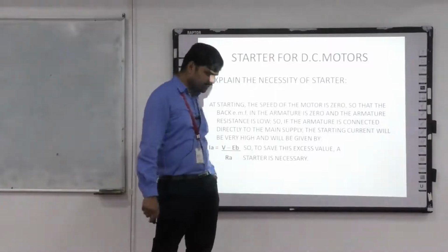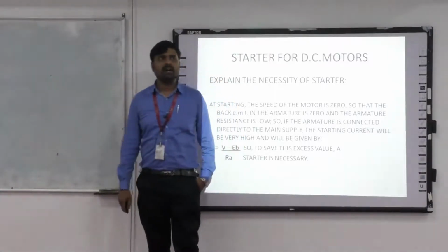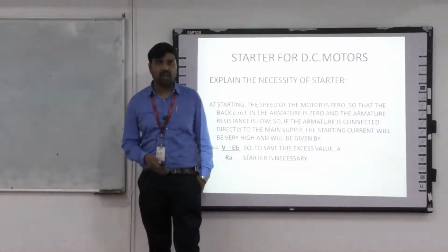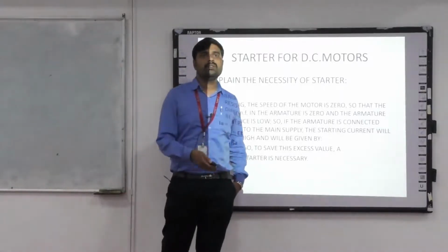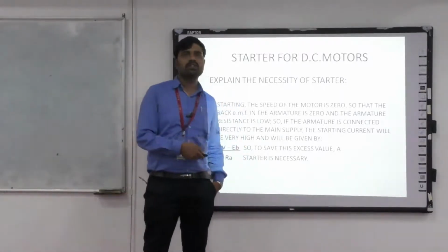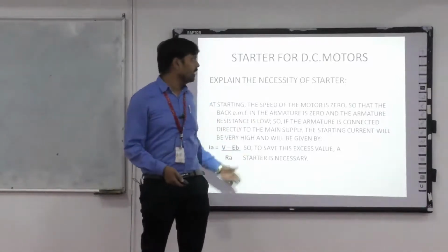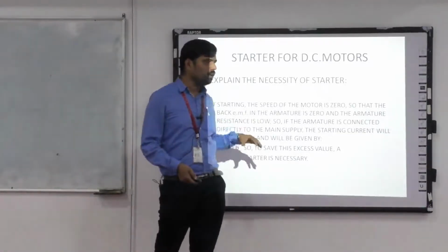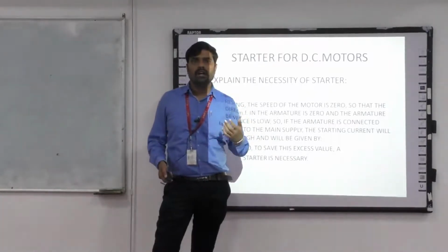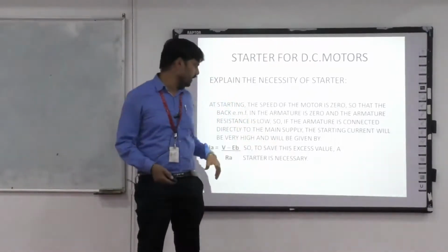This is the necessity of a starter. As I already told, if we are not using a starter, the back EMF is 0, and the current goes to 6 to 7 times the rated current. So what happens? The motor will get damaged. So we have to start the motor with a reduced current and reduced starting voltage.